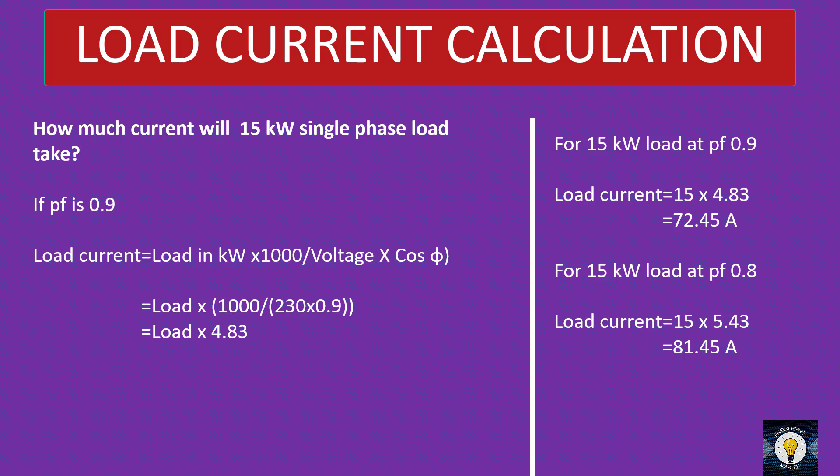One thing is evident: if the power factor is lower, the load draws more current from the line. You can see that at 0.8 power factor the current is 81.45 A — it is taking more current from the system. If your line voltage is 415 V and phase voltage is 230 V, just remember these multipliers and multiply your load to get the current. If your voltage is different, the equation remains the same — use it to form your own multiplier, which will help you find the current quickly.